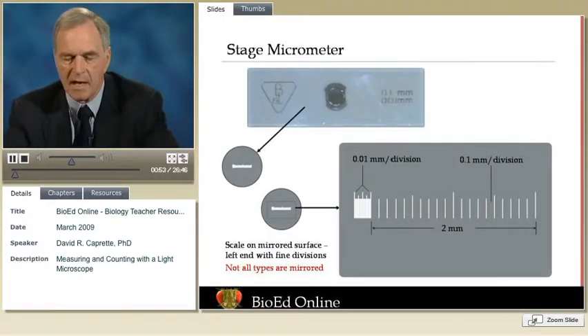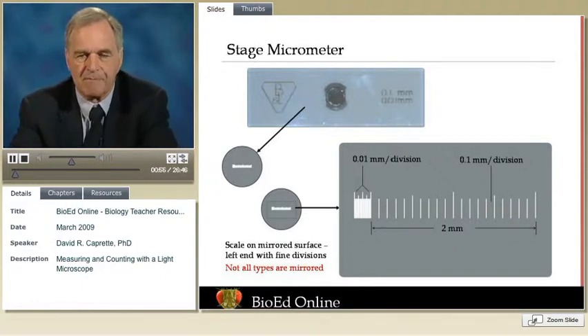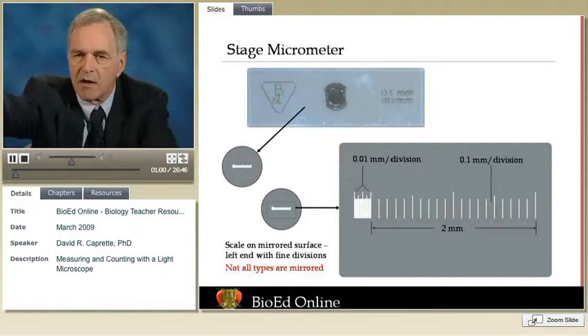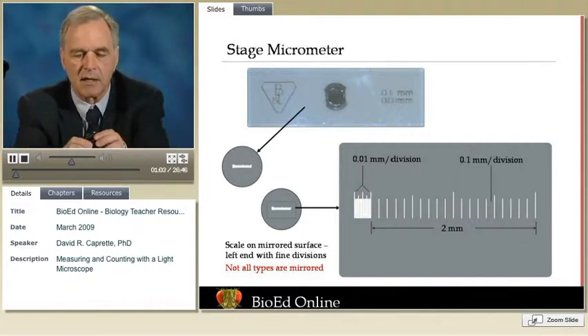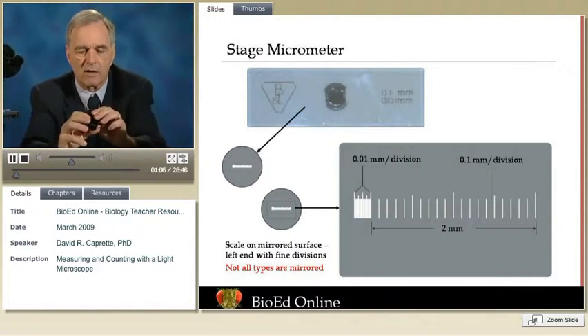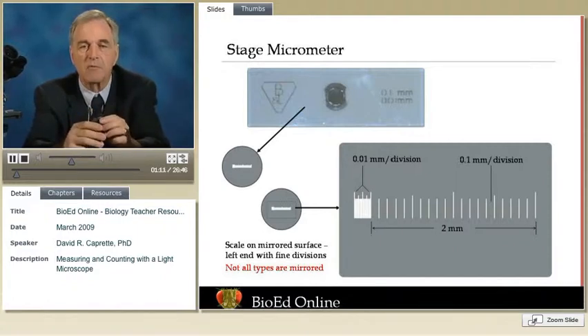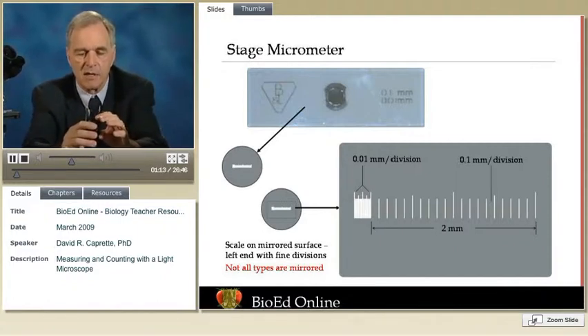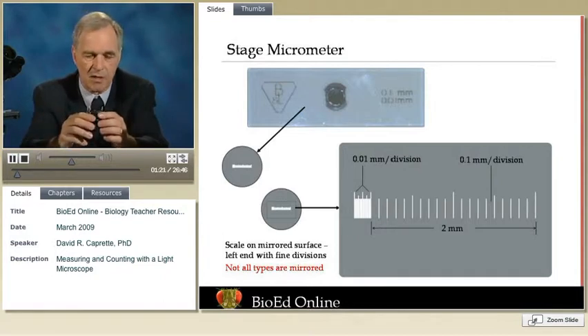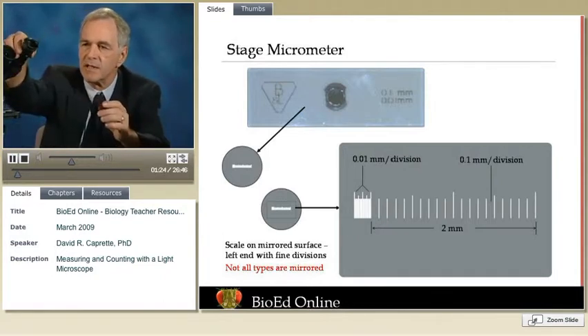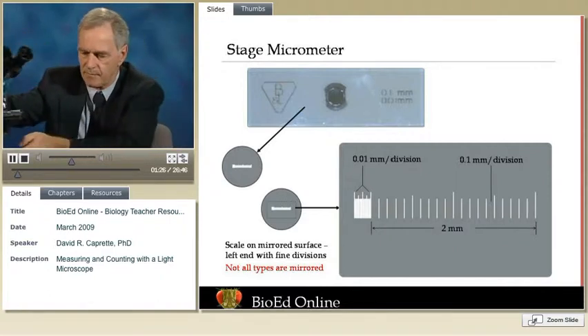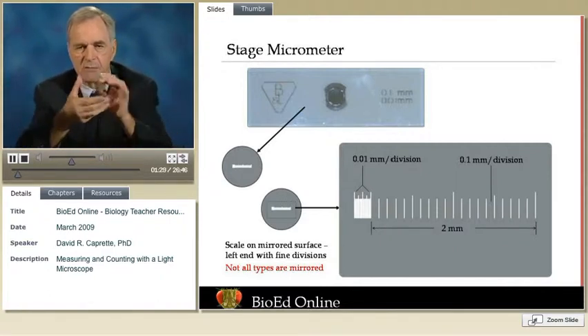leaf. To use a microscope as a measuring instrument, there's a couple things we need to do. One of them is to, in our eyepiece, obtain a scale called a reticle, which enables you to measure linear dimensions. Now, the reticles don't come pre-calibrated, and in fact, the calibration, that is the distance that each division of a reticle represents, changes depending on the objective lens that we use. So for a given objective lens, we calibrate the reticle by using something called a stage micrometer.